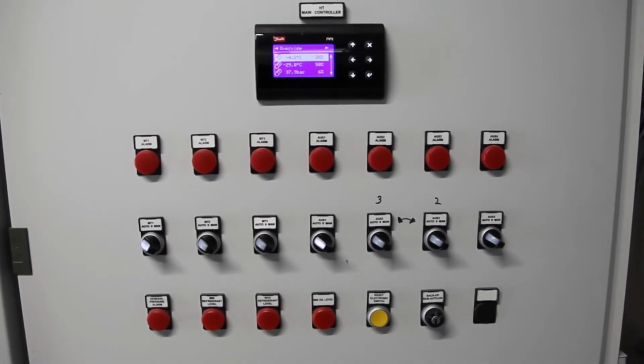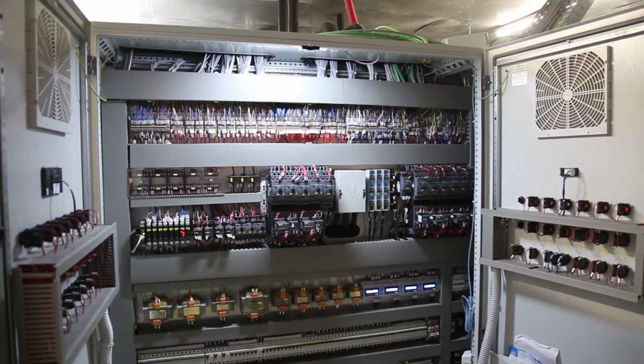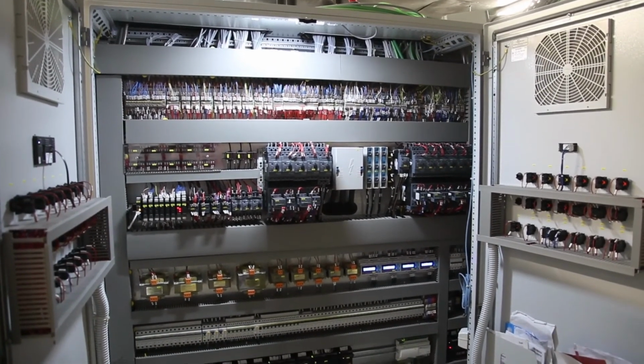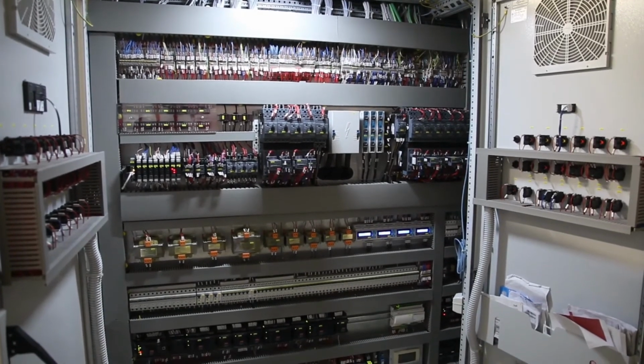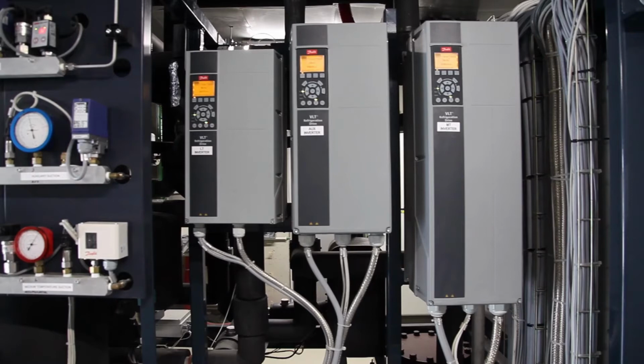And inside the cabinets, everything is nicely connected, and the controllers and the switches are located, and also the measurement equipment is attached to these parts. Here we have the frequency converters, giving each suction group the possibility to adjust the capacity. So we can adjust the capacity in accordance to the demand to maintain the pressure level of the 3 different suction groups, which are the freezing, which is called LT, the low temperature.